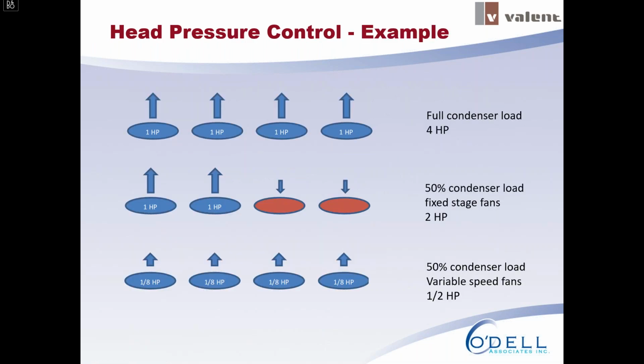So this last slide that I'm going to talk about here highlights an example of some of these different options and putting some horsepower numbers to what I just talked about. So that first row shows a condensing section at full load, and in this case we have 4 fans. They're all 1 horsepower. So if they're all running, you're using 4 horsepower. Pretty straightforward. Now let's consider a case where those 4 fans are seeing a 50% condenser load. So now the controls say, hey, we need to turn off 2 fans. We only have 50% load, so we need half the airflow. Well, 2 fans shut off and 2 fans run. So in this mode, you're using 2 horsepower.